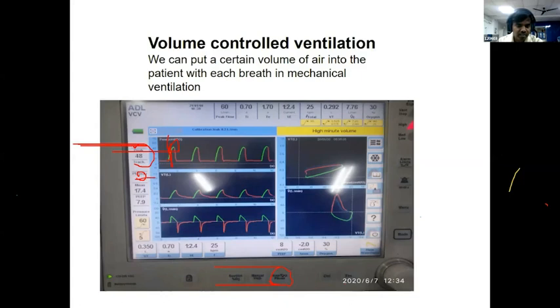In this ventilator, inspiratory and expiratory pause is there. You have to press the inspiratory pause. How do you press? When the inspiration starts here, you have to press, so a flat line will come. For a second, that will create the plateau pressure shown here. Are you clear? Yes, this is peak flow and this is the pressure limit. They have given a higher limit. We don't want this. So this is all about this.